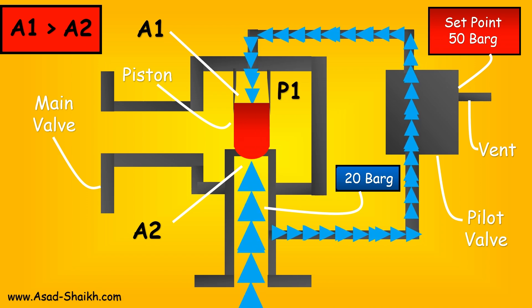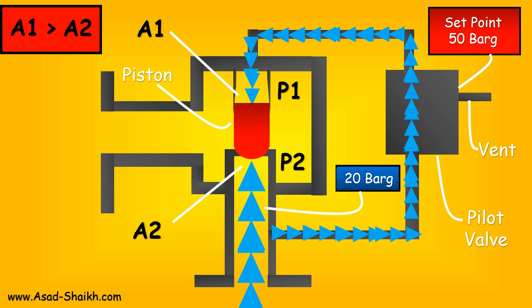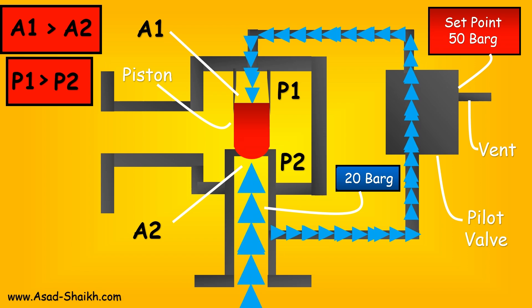Engineers have understood smartly that pressure is basically force applied on unit area. Because area A1 is bigger, pressure P1 is going to be greater than pressure P2 at the bottom of the piston. Thus P1 being greater than P2 will cause the relief valve to be in closed position when the inlet pressure is less.